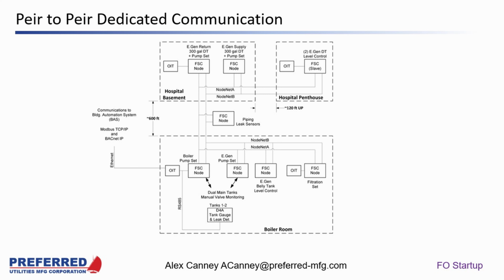Having this system where you can run a couple of communication lines up however many stories you need to the day tanks from the main tank and pump set area allows you to get the new controls up and running and tested before swapping over from the old system. That's a huge impact, because most hospitals already exist and are on aging systems that need to be retrofitted. So that's another advantage of doing it via communications.